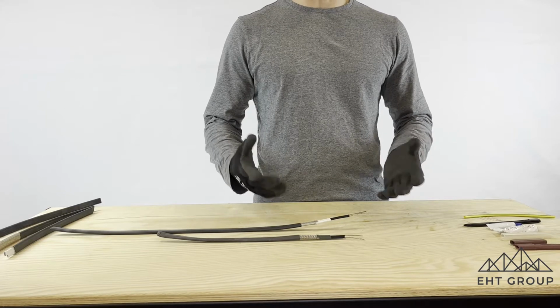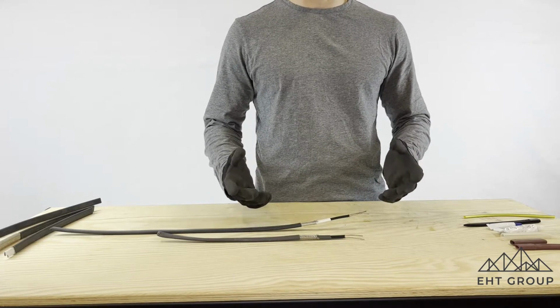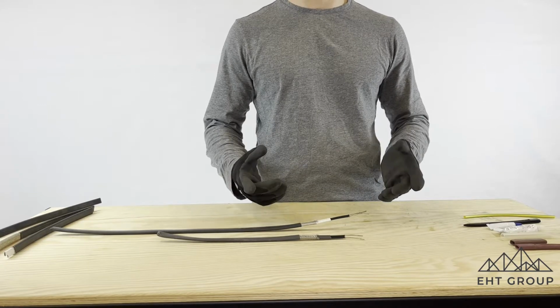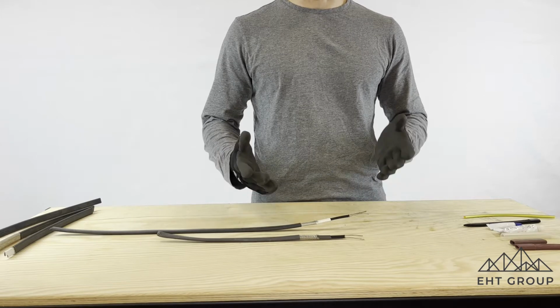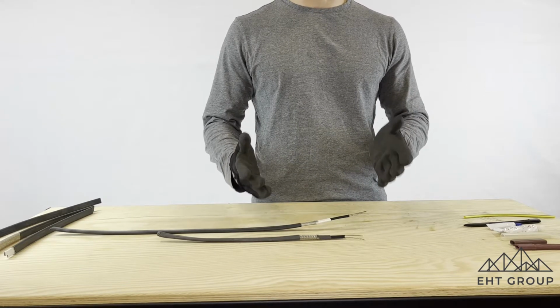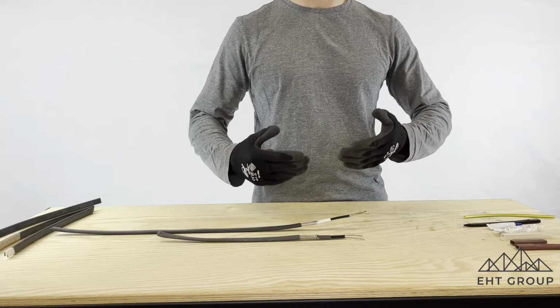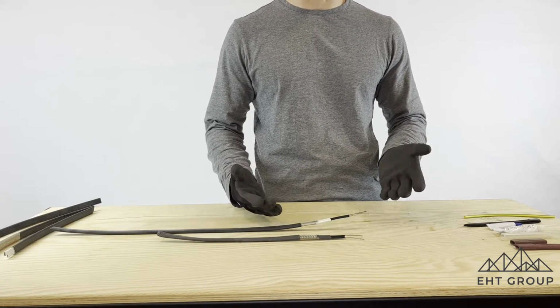And the reason that it does that is because the resistance of the heating cable is going to change based on the temperature that the cable sees. It's also referred to as parallel heat trace cable. So as a component of the cable is seeing colder temperatures, the resistance of the cable will actually decrease and the current draw in that particular section will actually increase, or generate more heat.